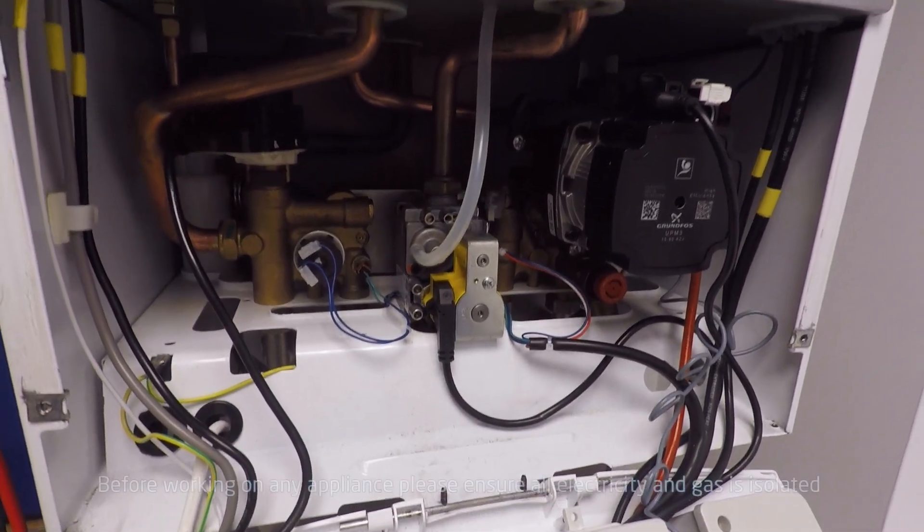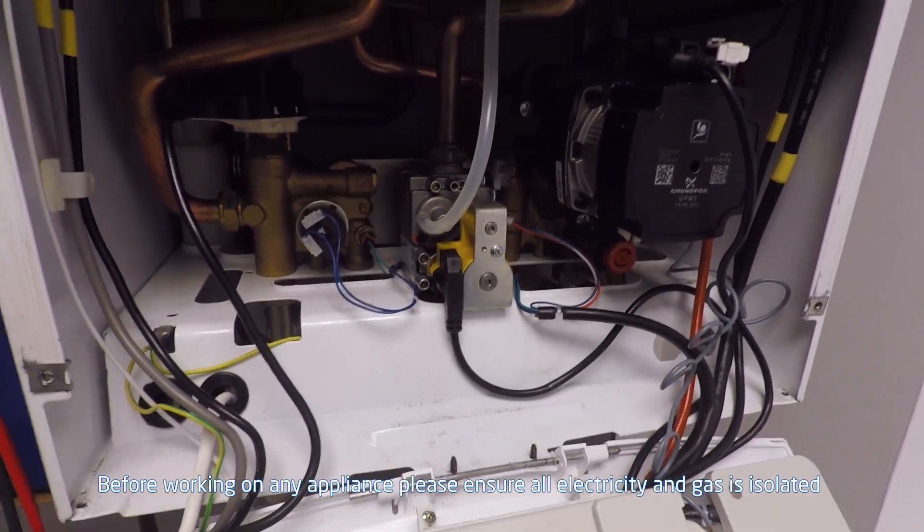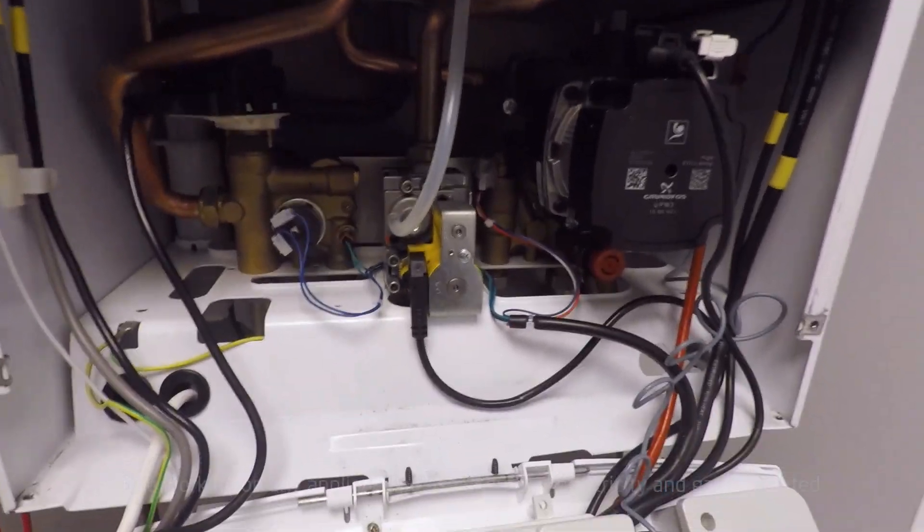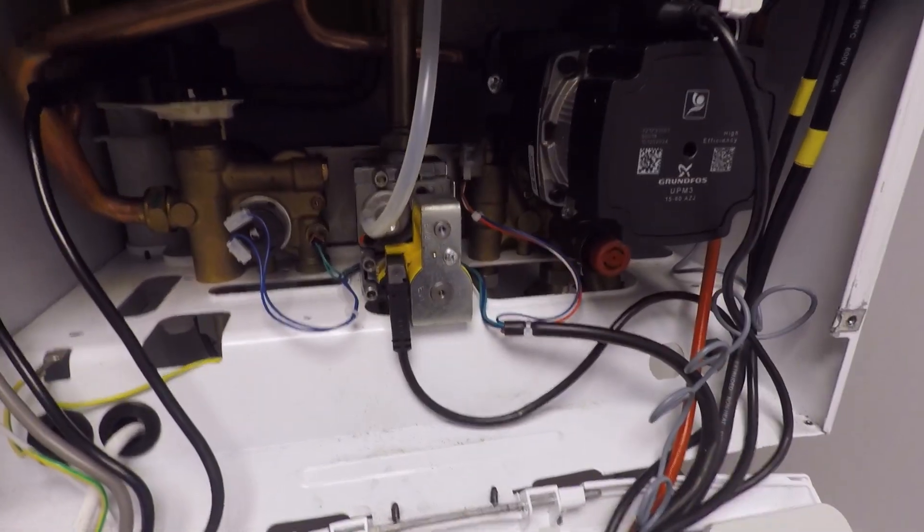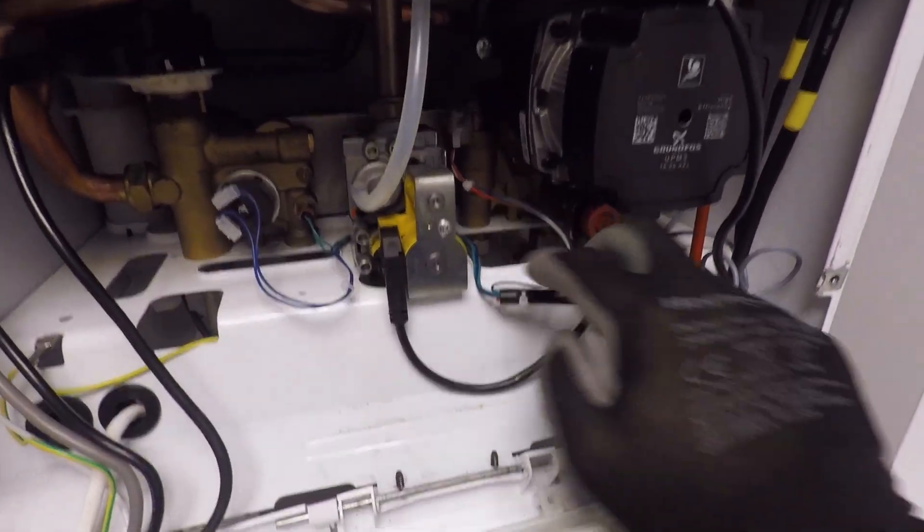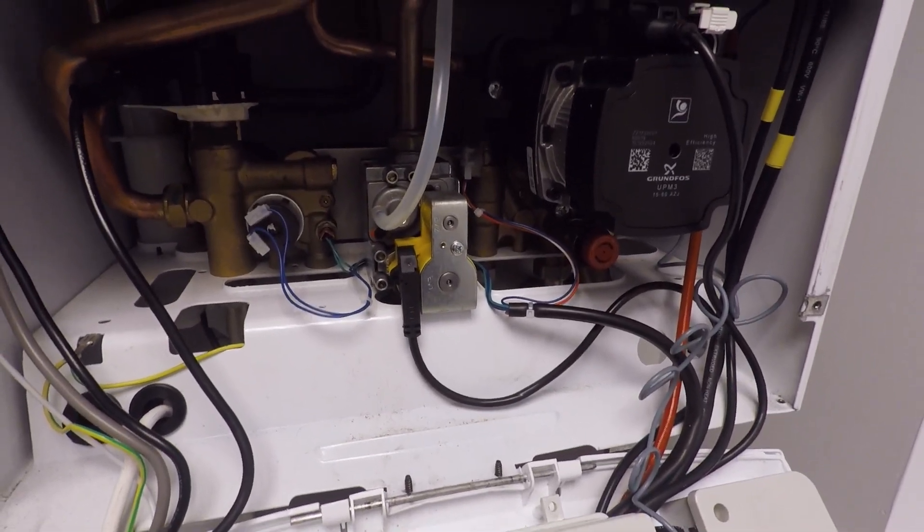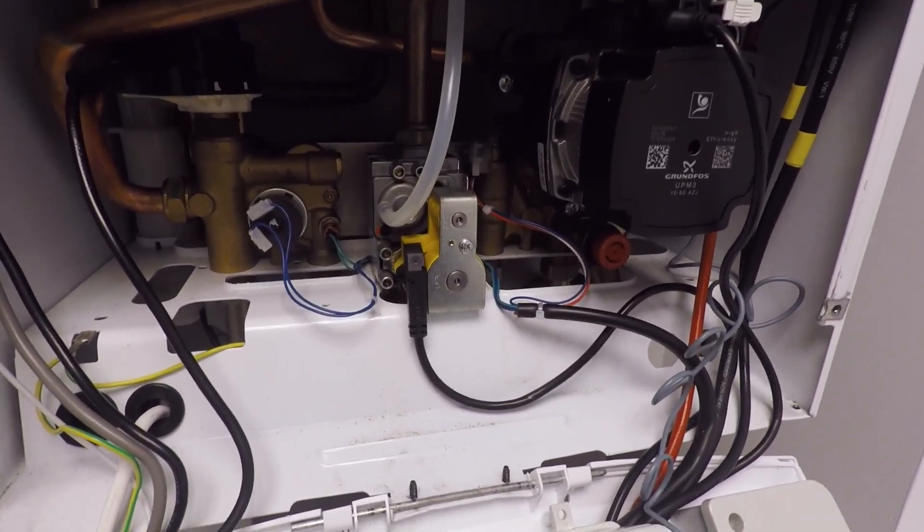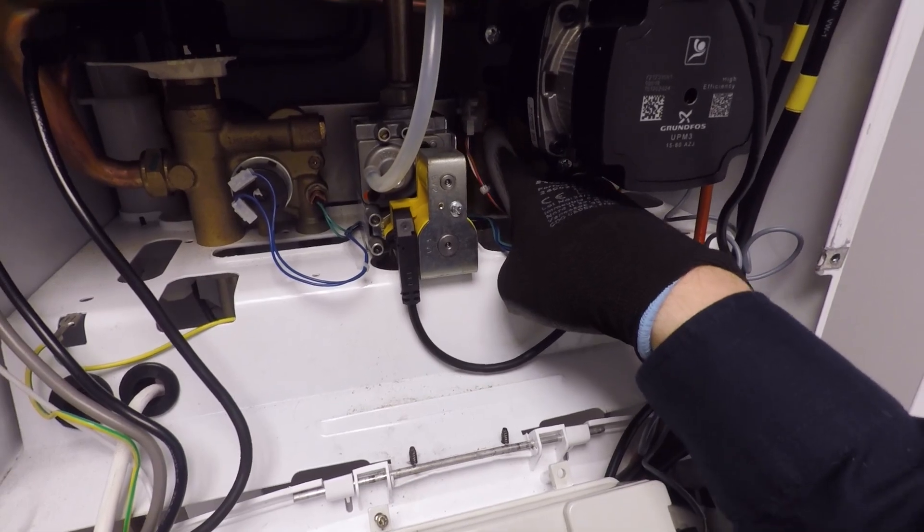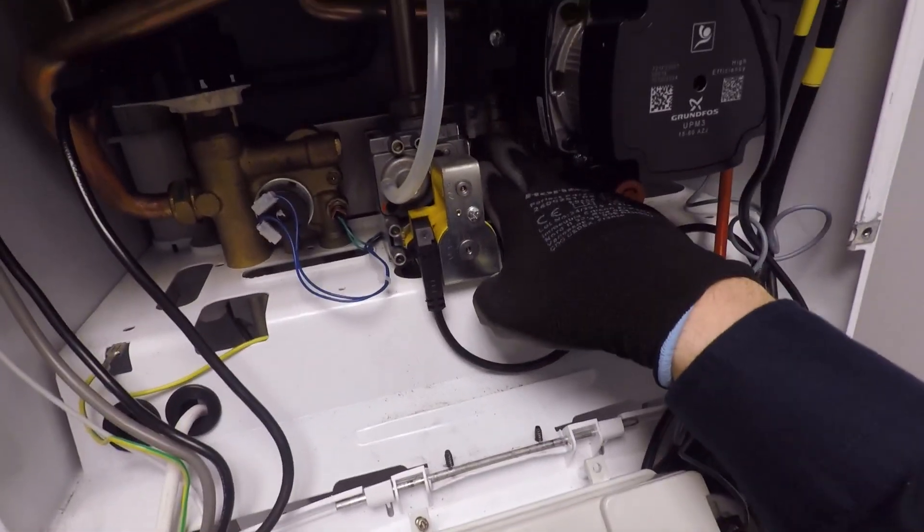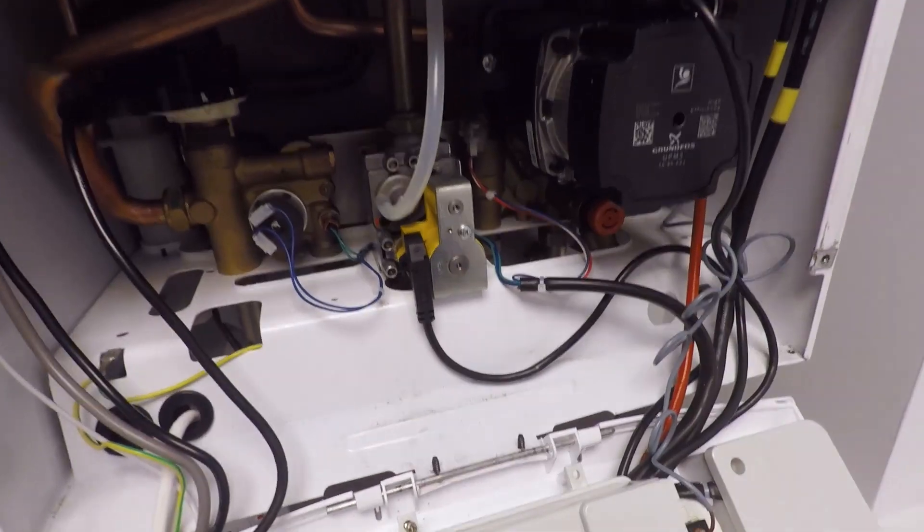Okay then, Anthony, we'll make a start. The Hall Effect sensor on the Duotec and the Platinum is used for hot water detection and there it is, sat right there on top of the hydraulic inlet assembly. It's the clear plastic one with the red, white and blue wires going to it. Some people call it a bobbin and some people call it a float switch because quite simply, there's just a magnet inside the hydraulic inlet assembly and as soon as the customer or yourself runs the hot tap, the magnet jumps up inside the magnetic field on the Hall Effect and the boiler recognizes the demand.